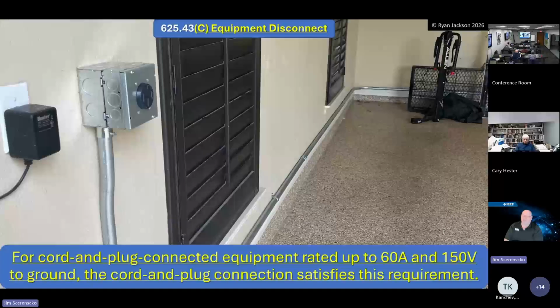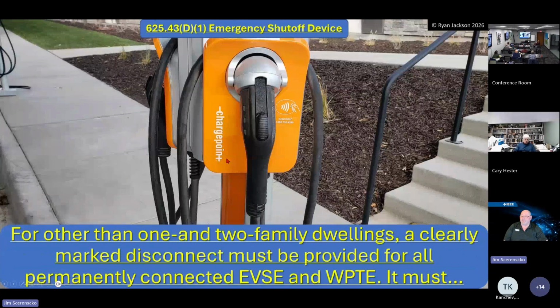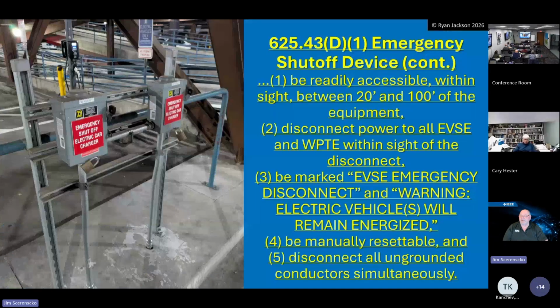Cord and plug connected equipment rated up to 60 amps and 150 volts to ground: the cord and plug connection satisfies the requirement for the disconnecting means. That's great, right? For other than 1 and 2 family dwellings, a clearly marked disconnect must be provided for all permanently installed EVSE and WPTE equipment. 625.43(D)(1), emergency shutoff devices: be readily accessible, within sight of between 20 and 100 feet of the equipment. So now you have to have an emergency shutoff.